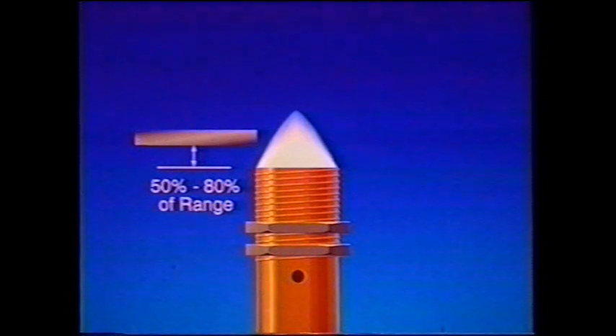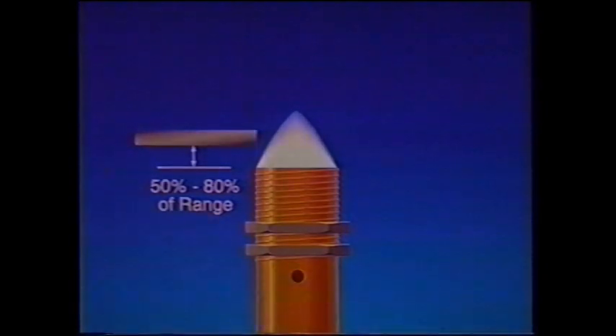The most obvious factor that determines the sensing range is the size of the switch itself. The strength of the radiated field is determined by the size of the core inside the switch. Larger switches have larger cores and therefore longer sensing ranges. Always select a proximity switch that is large enough to provide adequate range for the application. Good practice dictates that a proximity switch should operate at 50% to 80% of its range to avoid marginal conditions.